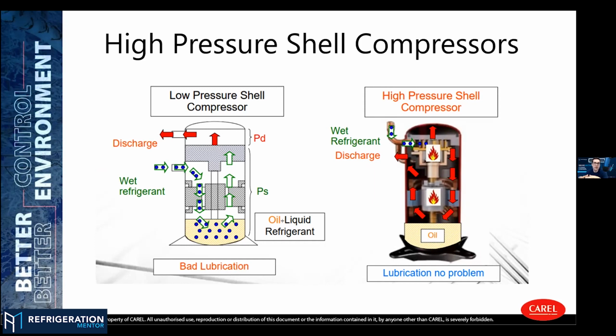What is your check? One of the things that you'll have to do on low pressure, you always want to check your discharge temperature on the discharge line. Usually on the Copelands, it's 6 inches down. I teach on this one here. What is your discharge temperature check you're looking for, and what temperature would you recommend to keep below? Okay, yeah. This kind of compressor in general is rated to work at a discharge temperature around 100 degrees Celsius. So the discharge temperature should be around 100 degrees or below.